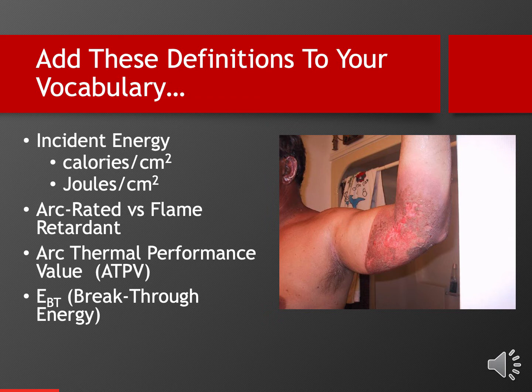And that would give you 1.2 calories of heat, which would give you the onset of a second-degree burn. For the purposes of our discussion, we're going to always be considering arc flash hazards to be 1.2 calories or more. A number that you won't find in the regulations that I recommend you make note of is 10.7 calories per square centimeter, will result in a third-degree or an incurable burn.